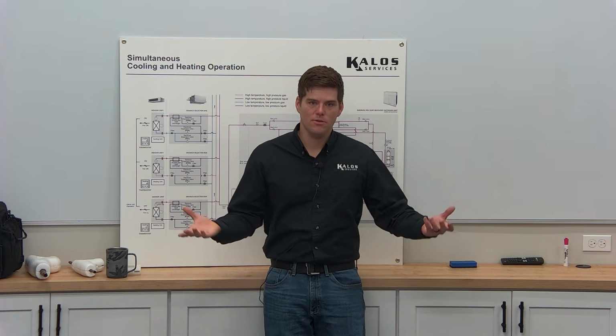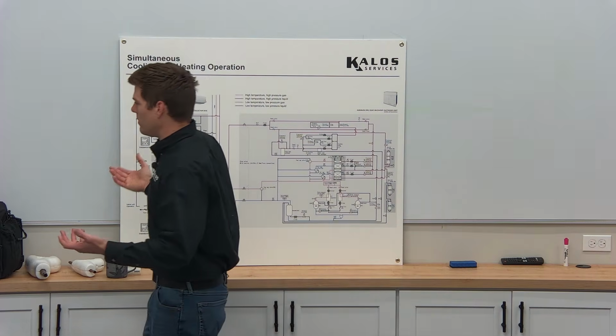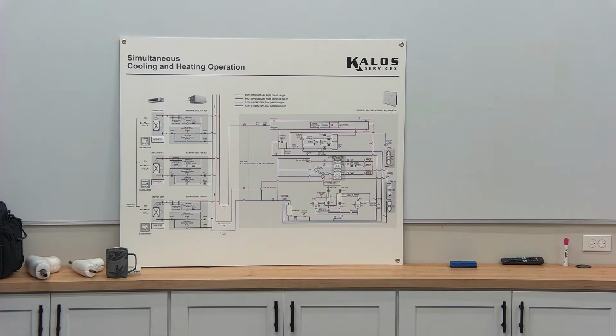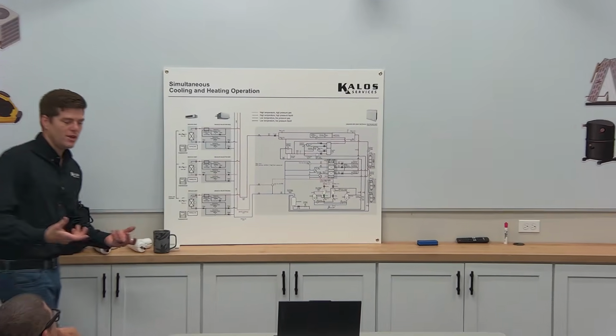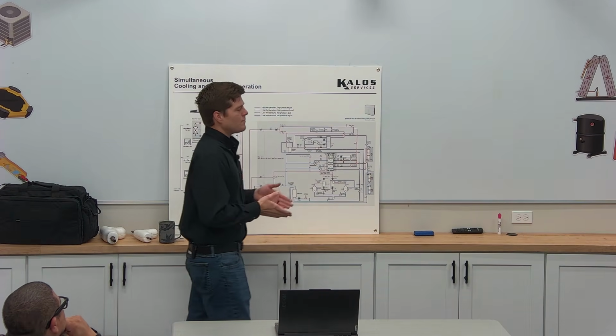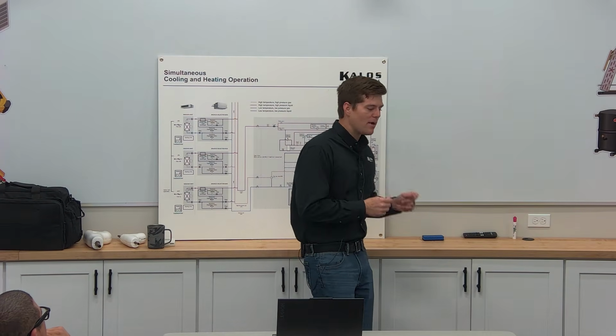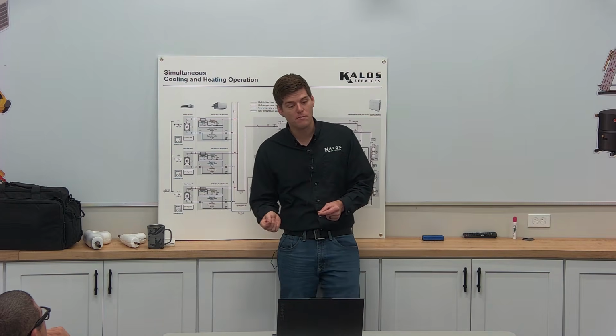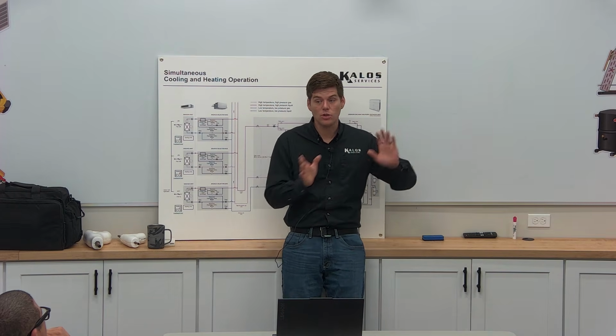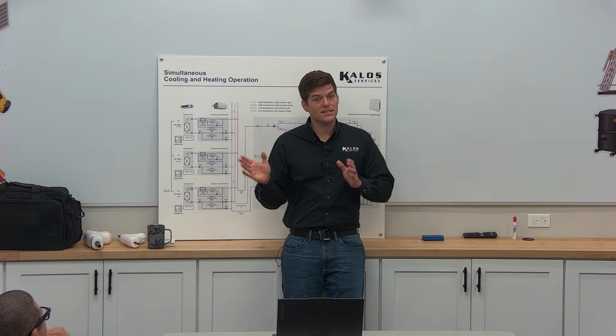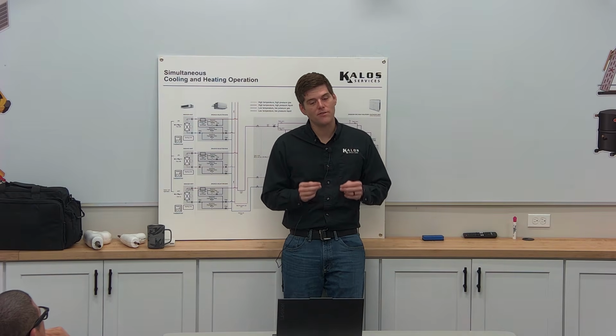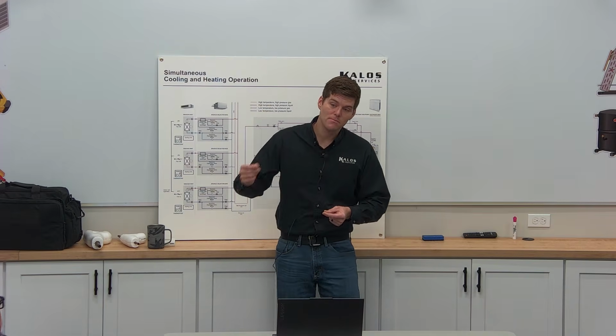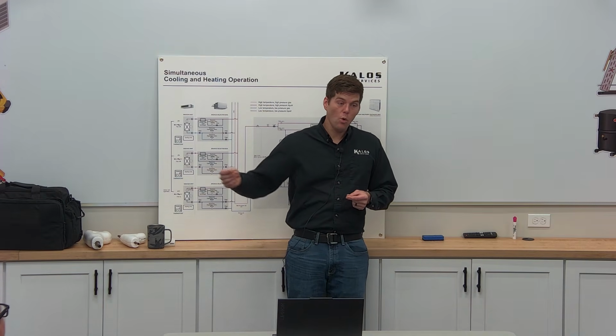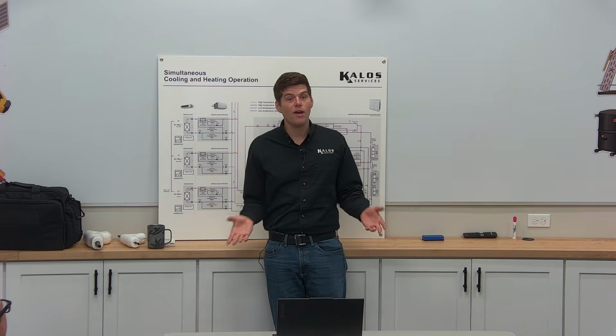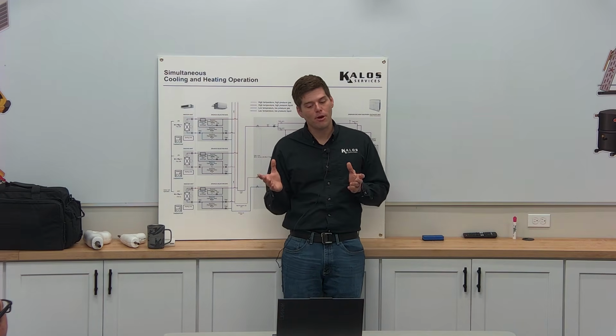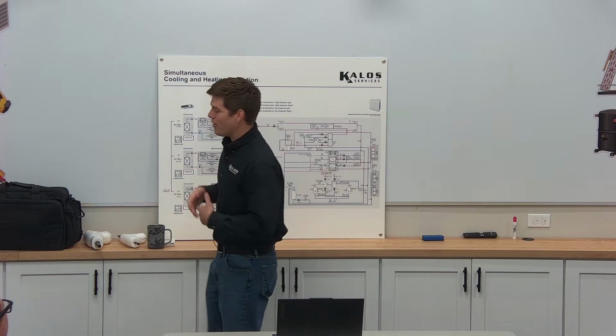And why do you need variable? Why can't we just run it at one speed and then determine who opens and who closes? It's about efficiency. VRF systems were designed to supply just the right amount of liquid refrigerant or hot gas, depending upon the mode, that is needed. That's it. No less, no more. It's designed to only use the exact amount of electricity needed to meet the demand of the indoor unit or indoor units. VRF, that's the variable part, the refrigerant part, kind of self-explanatory, and the flow part.